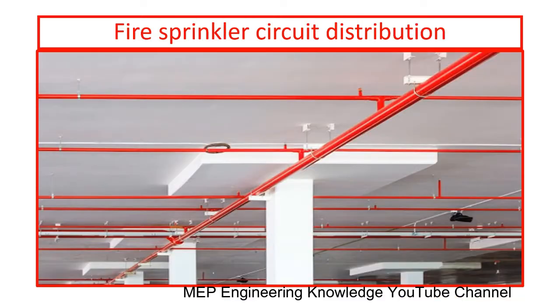A typical arrangement of sprinkler piping and sprinkler head is shown for your quick understanding. Here you can see an upright sprinkler is provided and a main header pipe is running, the branches are taken, all the supports are evenly provided, and the pipes are painted neatly in red color. This is how all the sprinkler pipelines should look. It has to be in a straight line. All the sprinklers have to be evenly spaced as per the requirement and should have proper coverage. In the drawing, it will be mentioned as the umbrella coverage drawing.